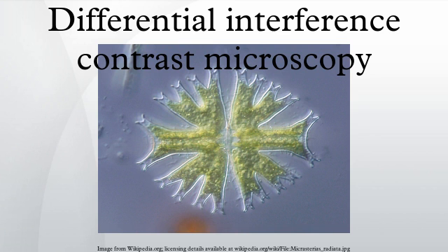Step 4 — The rays travel through adjacent areas of the sample, separated by the shear. The separation is normally similar to the resolution of the microscope. They will experience different optical path lengths where the areas differ in refractive index or thickness. This causes a change in phase of one ray relative to the other due to the delay experienced by the wave in the more optically dense material. The passage of many pairs of rays through pairs of adjacent points in the sample means an image of the sample will now be carried by both the 0 degree and 90 degree polarized light. These, if looked at individually, would be bright field images of the sample, slightly offset from each other. The light also carries information about the image invisible to the human eye — the phase of the light. This is vital later.